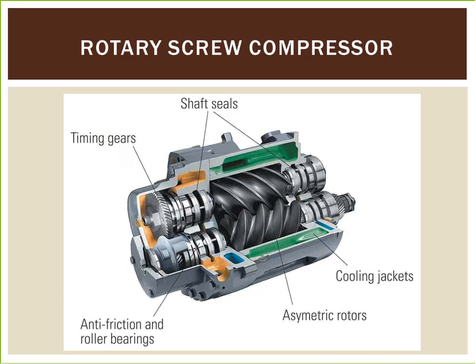Rotary air compressors are positive displacement compressors. The most common rotary air compressor is a single-stage helical or spiral lobe oil-flooded screw air compressor. These compressors consist of two rotors within a casing where the rotors compress the air internally. There are no valves. These units are basically oil-cooled with air-cooled or water-cooled oil coolers where the oil seals the internal clearances.